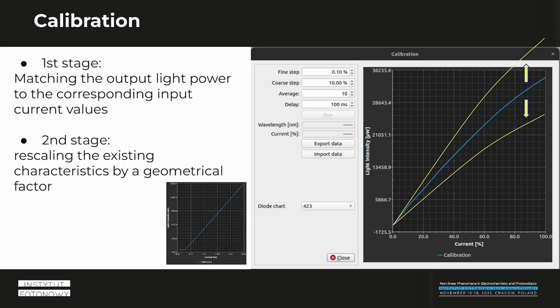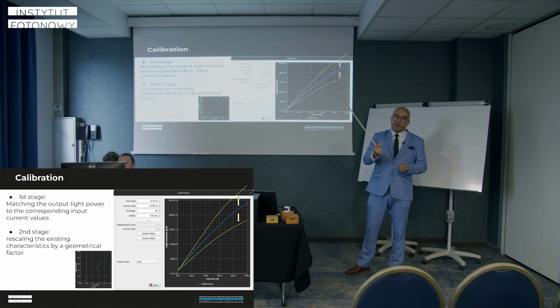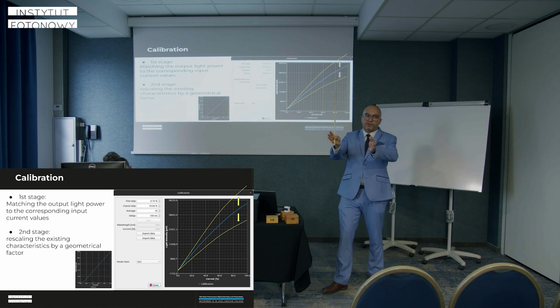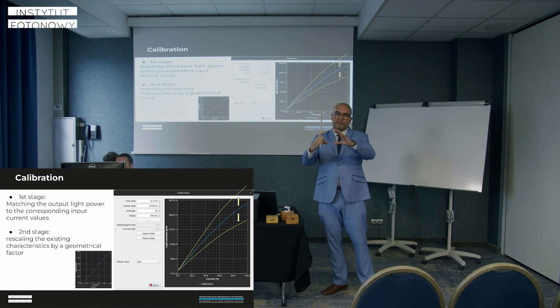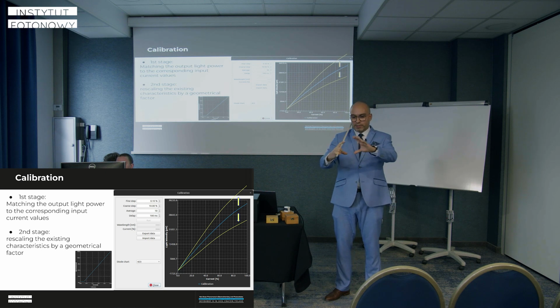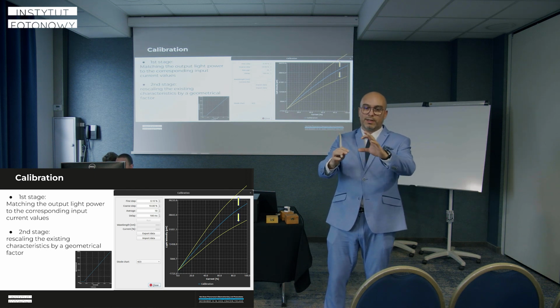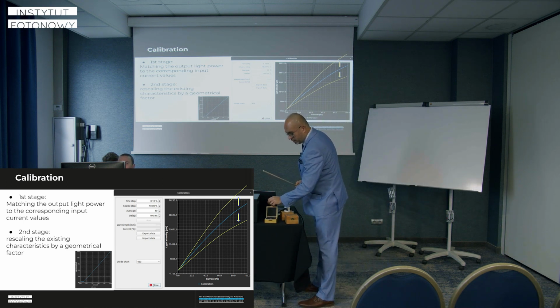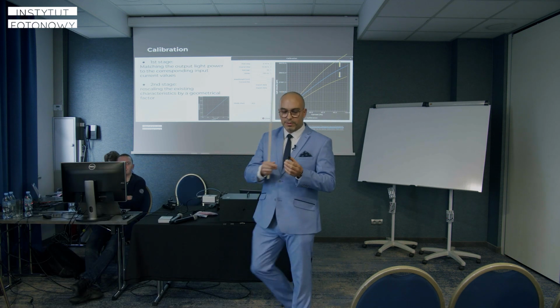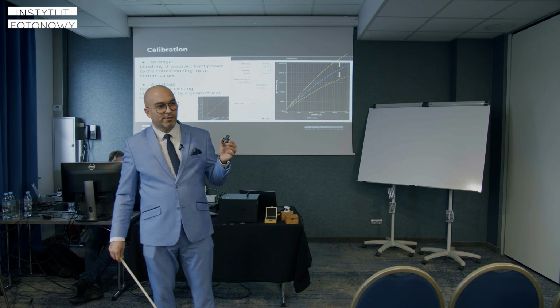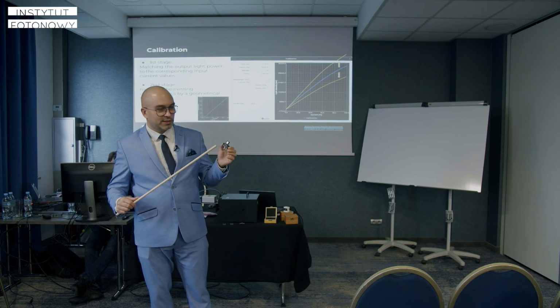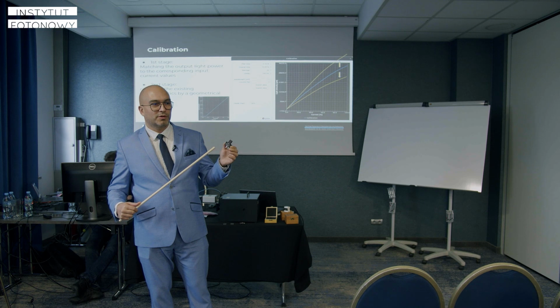The second stage of calibration is when we change the geometry of our measurement, because if we move the sample closer or farther from the light source, there is a cone of light from the LED that we focus with a lens. It matters how much light of this cone we take in our lens, then how much light we focus on the sample and how much light reaches our calibrator. And we use a silicon photodiode as the measurement head of our calibrator with an area of 1 square centimeter. So the light power which is measured by the photodiode is in microwatts, and at the same time we can express it as milli or microwatts per square centimeter.